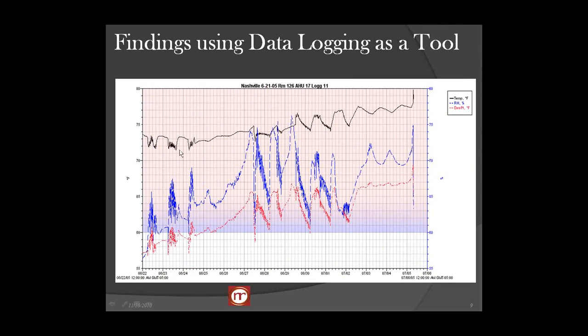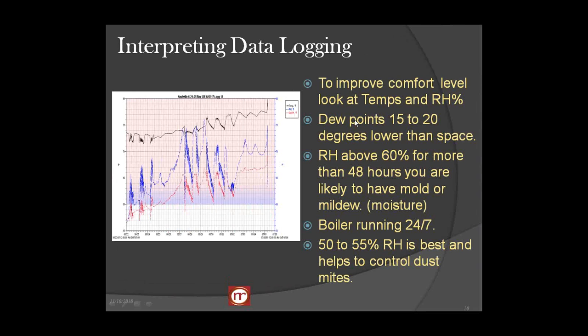And with data loggers, you're looking at three things: relative humidity, that's in the blue, space temperature in the black, and dew points in the red. Okay, now if we simply narrow that and look at the temperature and the relative humidity, you'll notice that during this time we played around a little bit with them just to see the effect of humidity. I can tell you that dew points need to be 15 to 20 degrees lower than the space temperature. In this case, they're not.